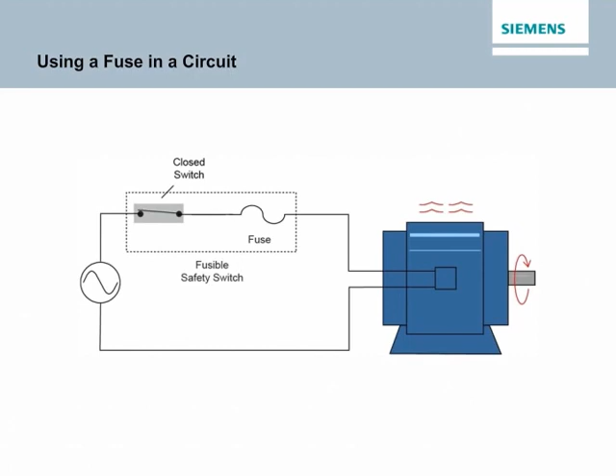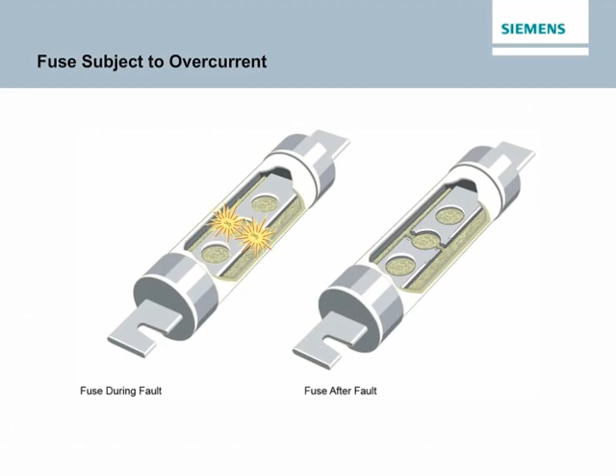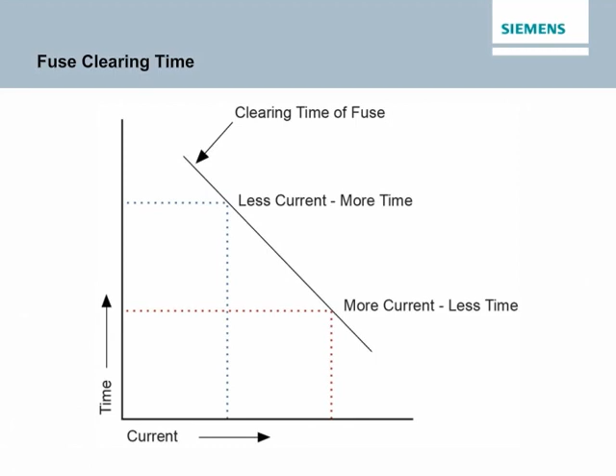Current flowing through the fuse element generates heat, which is absorbed and dissipated by the filler material. When an overcurrent occurs, temperature in the element rises. In the event of a transient overload condition, the excess heat is absorbed by the filler material. However, if a sustained overload occurs, the heat will eventually melt open an element segment. This will stop the flow of current. Fuses have an inverse time-current characteristic. The greater the overcurrent, the less time it takes for the fuse to open. This is referred to as the clearing time of the fuse.